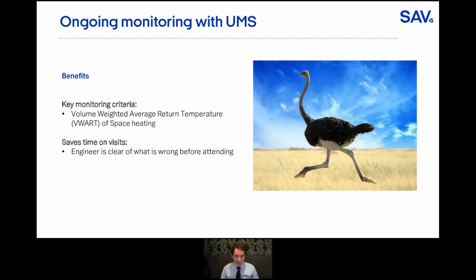We've looked at the commissioning side, the setup side, but there's also a benefit in the ongoing monitoring. With the Kamstrup meter, you can see what's happening on that secondary side, but also you've got some key performance criteria. You can look at your volume weighted average return temperature for that space heating. So you can compare that with your primary side, and then you already know where that return temperature issue may be coming from. Is it coming from the DHW because you can't see it on your space heating, or is it definitely coming from your space heating? This means that you can then send engineers to site knowing what they're going to be looking for with the right parts, so you can save visits, and you can save the complexity of trying to work out what's happening. So finally, we can take our head out of the sand and actually know what's happening.